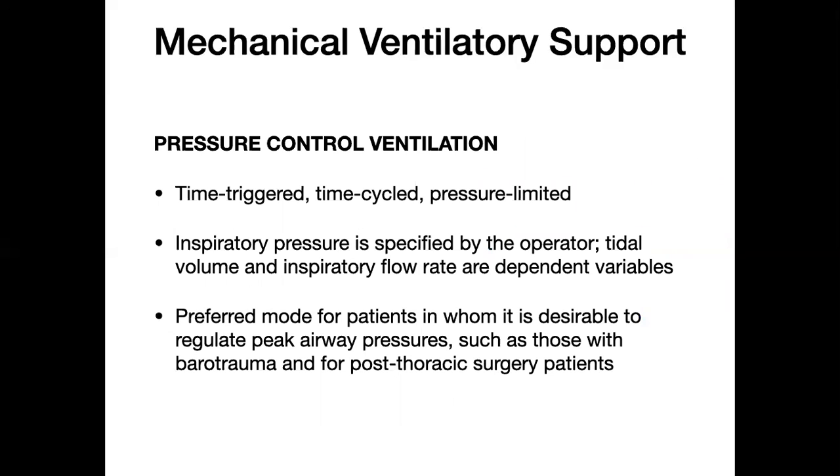The other form of ventilation is the pressure control ventilation, which is time-triggered, time-cycled, and pressure-limited. The inspiratory pressure is specified by the operator. The tidal volume and the inspiratory flow rate are dependent variables. And this is the preferred mode for patients in whom it is desirable to regulate peak airway pressures, such as those with barotrauma and for post-thoracic surgery patients.